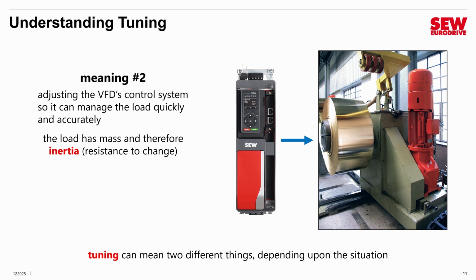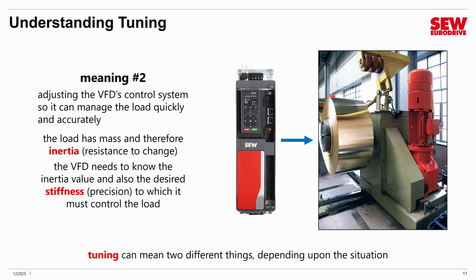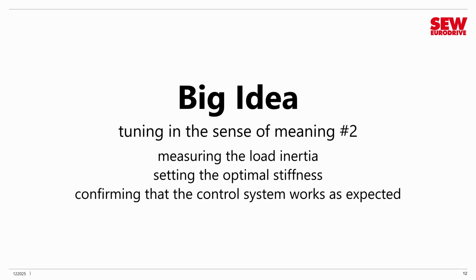That is inertia. Whenever you have a lot of inertia out there on the load, the VFD could have some trouble controlling it if it doesn't know how much inertia is out there. The VFD therefore needs to know the inertia value in order to control the load properly. So it has to be entered in or measured. You also have to do something else. You also have to tell the VFD what stiffness you want when you're controlling that load. Stiffness is the precision by which you're controlling the load. Are you starting and stopping it on a dime, or does it not matter a whole lot? Every application has its own unique value. When you set it, that is part of the tuning process. So another big idea here: tuning in the sense of meaning number 2 means, one, measuring the load inertia or entering it in, and two, setting the optimal stiffness.